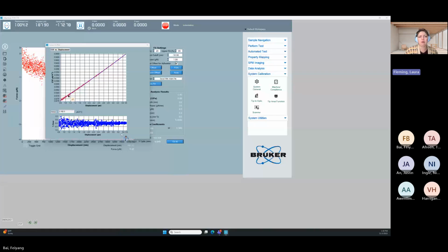And then we should also be looking at the red. Now, I see some low frequency vibrations getting through, which is pretty standard for the TS77. What I'm looking for here is if there's a weird spike in noise, or if it's really noisy the entire way, or if there's a weird discontinuity or curvature. Those are all red flags that, oh, maybe my calibration file isn't loaded, maybe something else is going on. I should email Laura or the global tech support team.